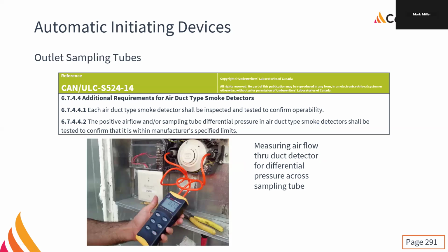And then there's our manometer test, right? We've got 0.2 on that, and that's usually measured in inches of water column, I think is the usual measurement. It's because, well, instrumentation. They're measuring it or whatever. So this is a System Sensor detector, right? Duct smoke detector, right? And we can see all our connections are in here, and it's a completely separate compartment where the wires run through. That is fully sealed so that we don't have any air getting out from in here. And it even has a set of contacts. If you pull the cover, we get a trouble on it. Perfect.